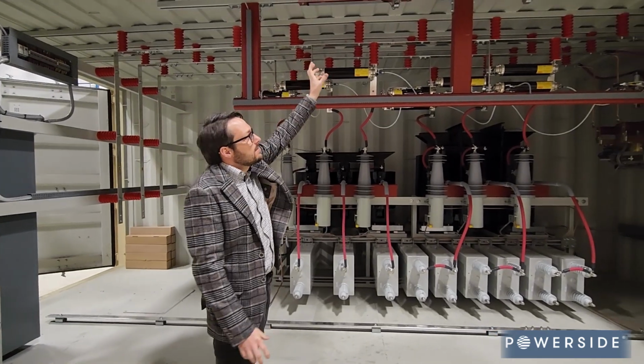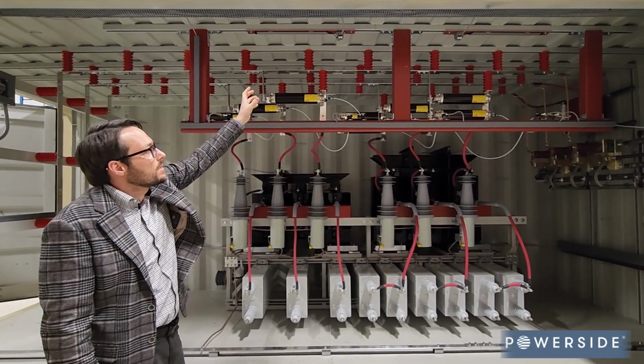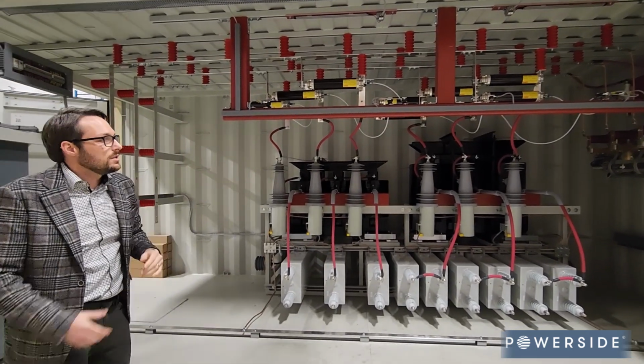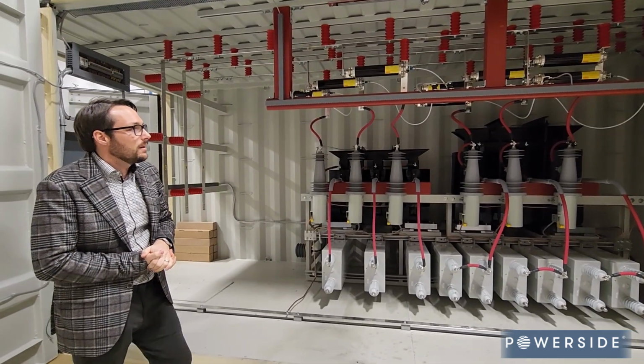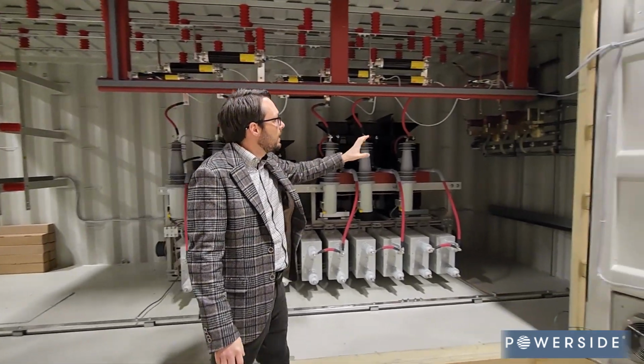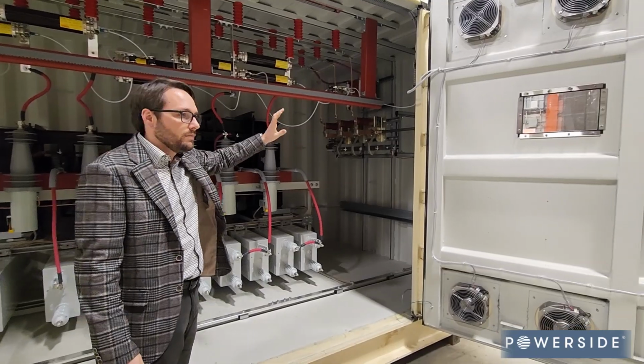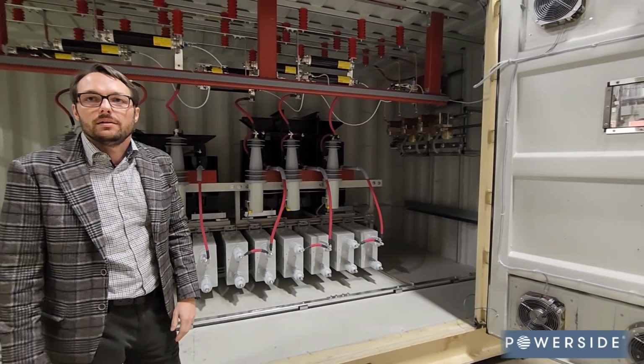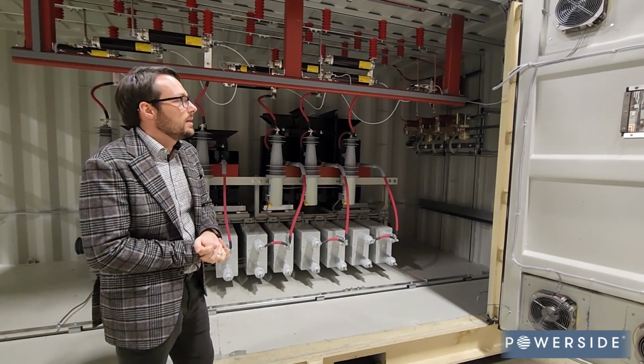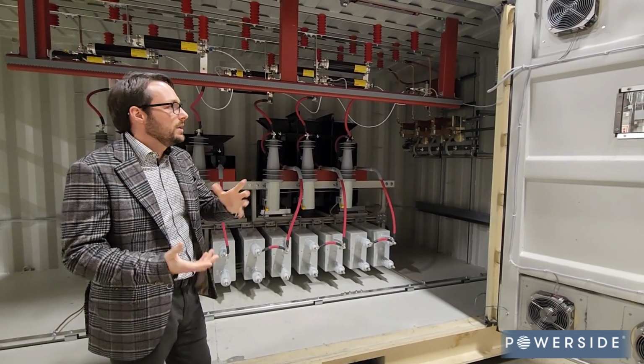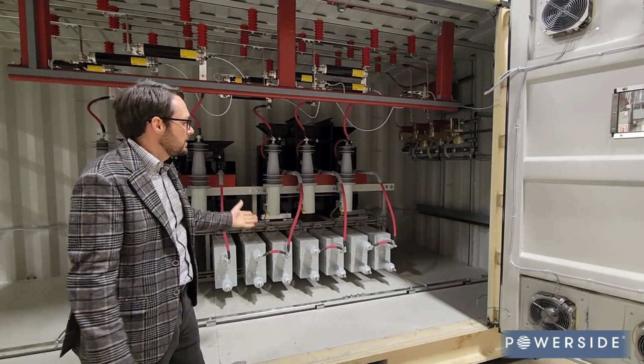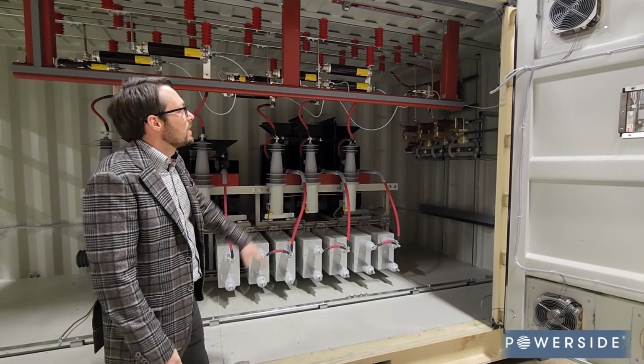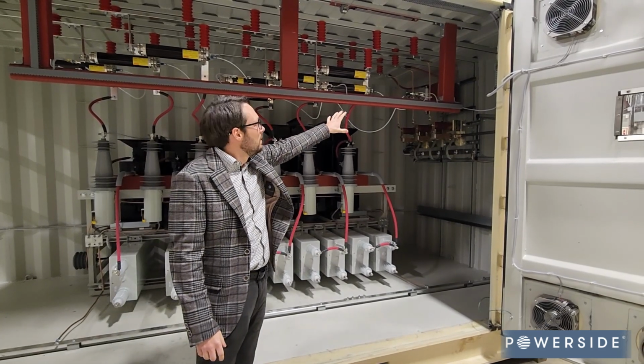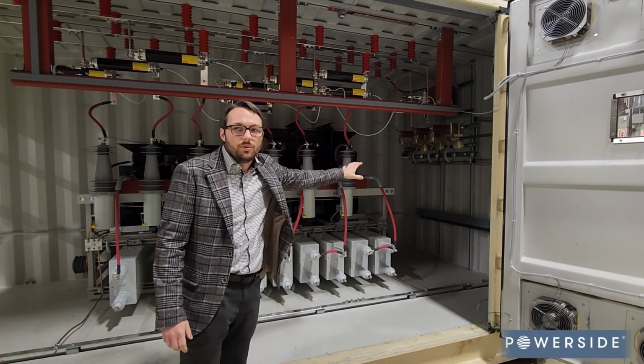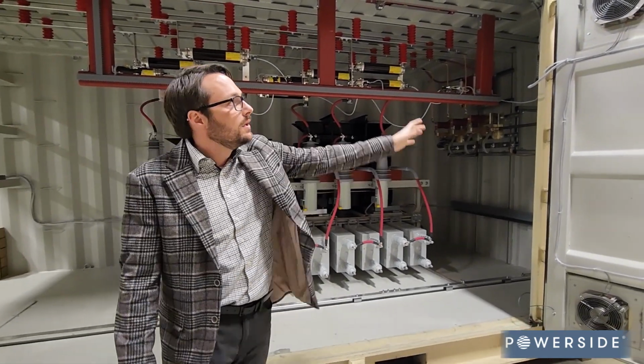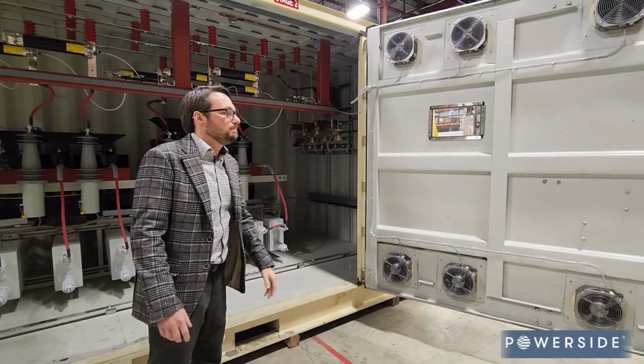We have lights inside here, which the client had requested, as well as anti-condensation heaters for the bank. And then as we move over on this side, we've got our ground switch here. So of course we use this before opening the doors, and for the Kirk key interlock scheme, we'll close the ground switch, and then we can get into the bank and access or service any of the components needed. We've got a control power transformer up here, which is providing the 120 volts for the control power, which is also powering these lovely fans for ventilation.